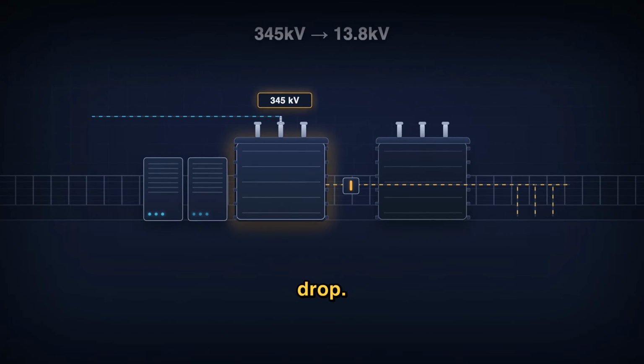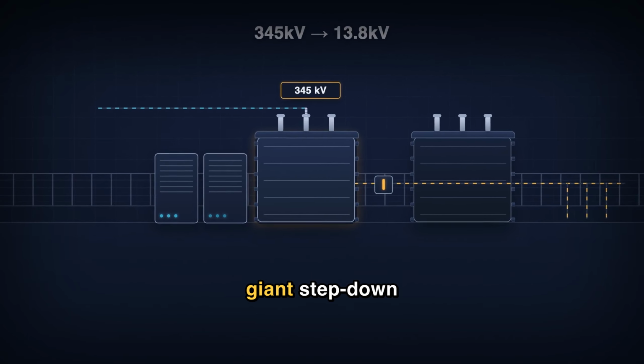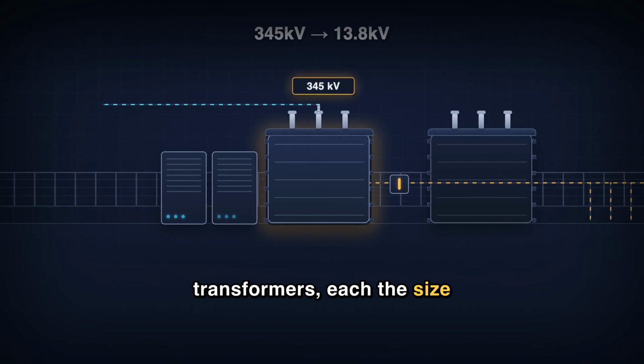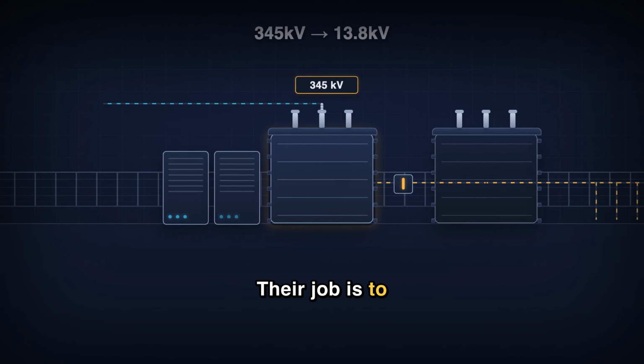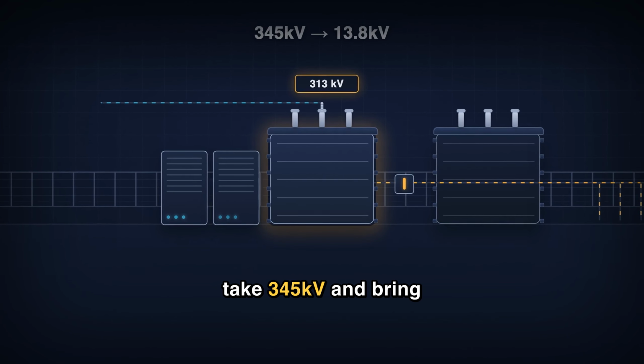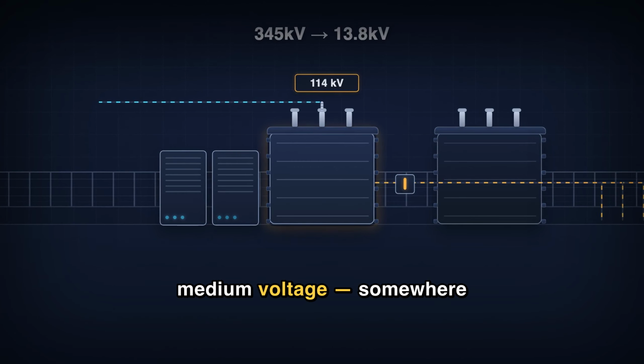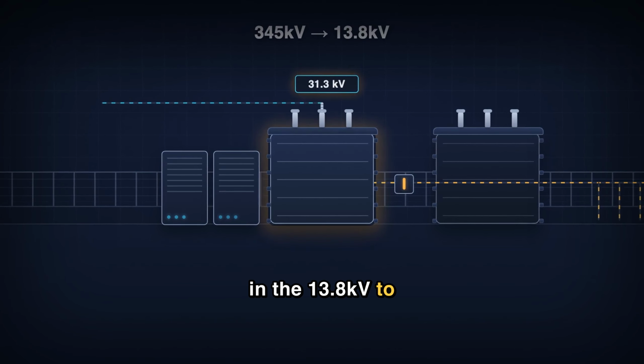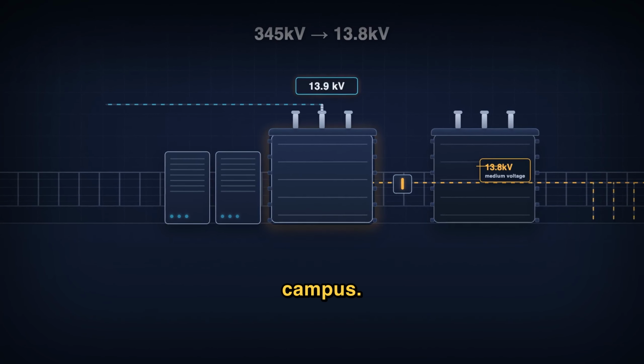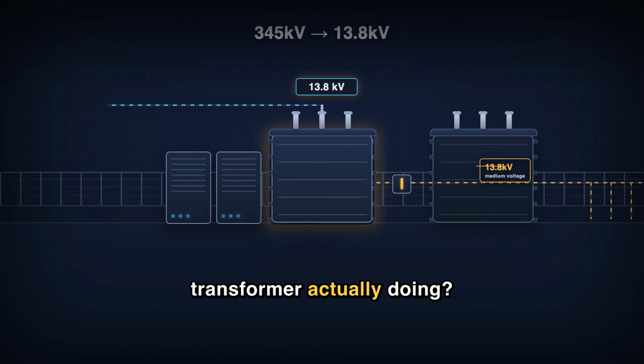Now the first big drop. Inside the substation sit giant step-down transformers, each the size of a small house. Their job is to take 345 kilovolts and bring it down to a medium voltage, somewhere in the 13.8 to 34.5 kilovolt range for the campus. So what is a transformer actually doing?